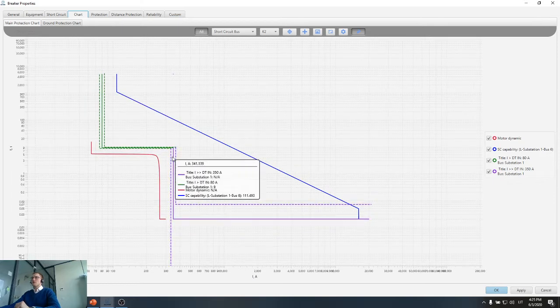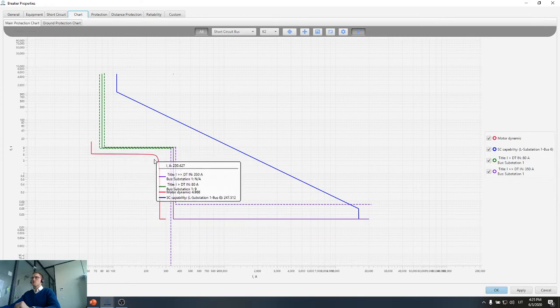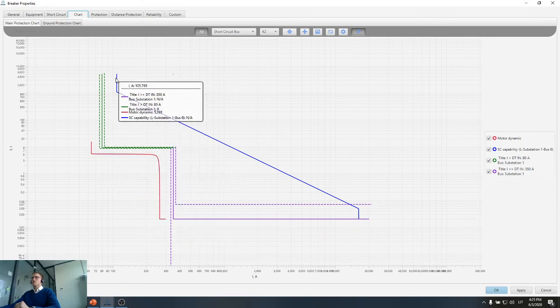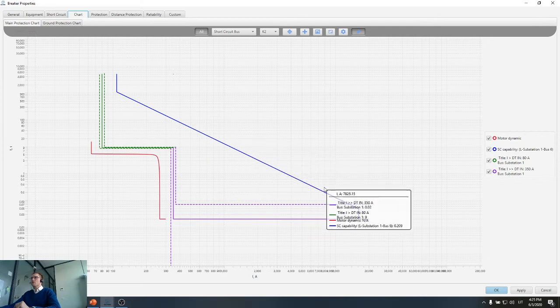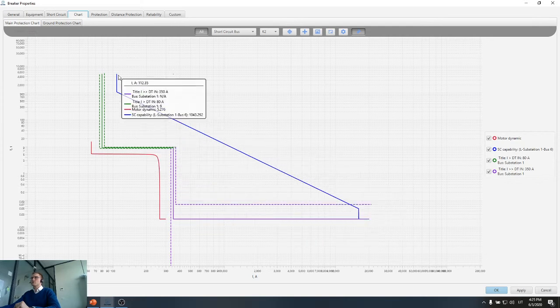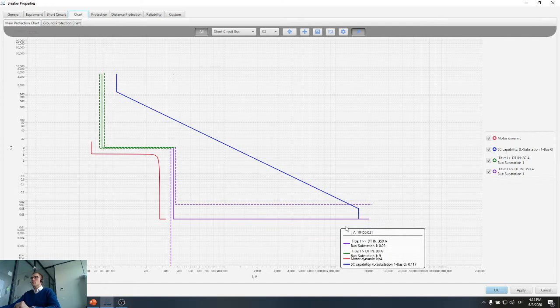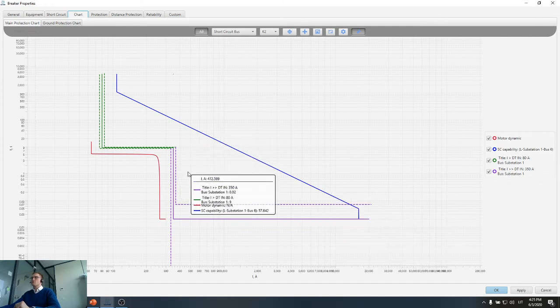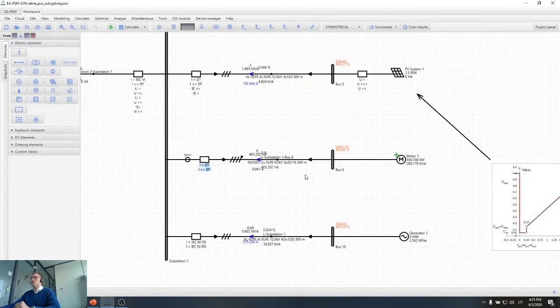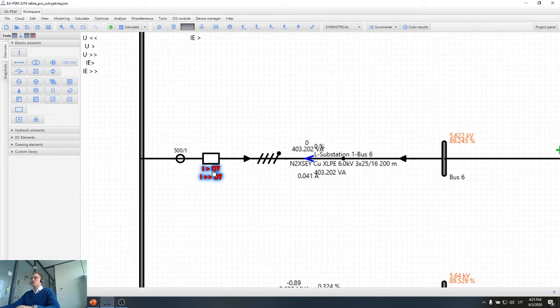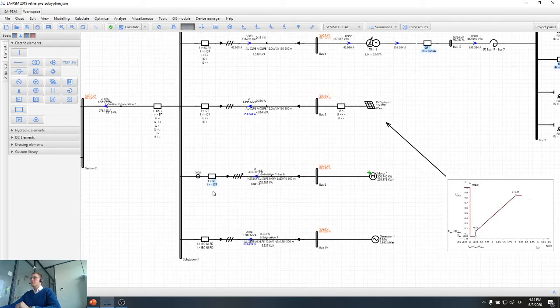that this numerical relay won't trip during motor starting. It will also protect my motor in case of short circuits, because at all points my TCC curve is smaller than the capability curve of the cable. So here we go, we have set two stages for the numerical relay.